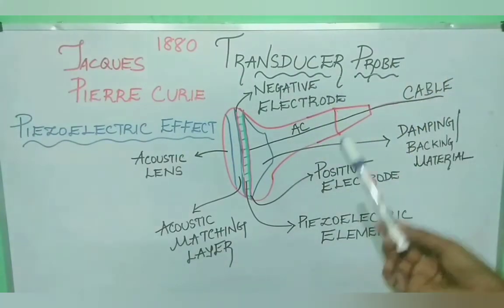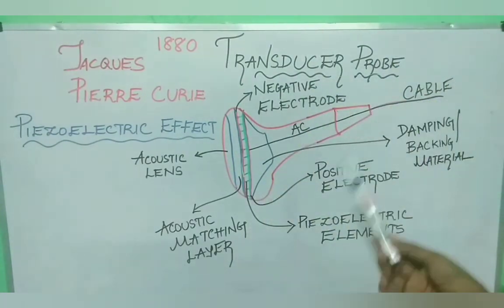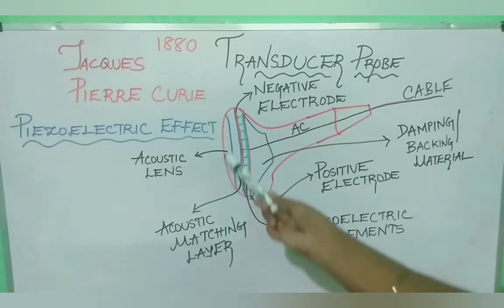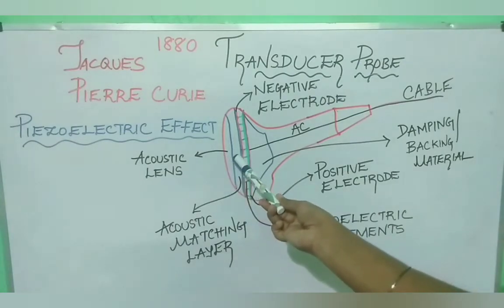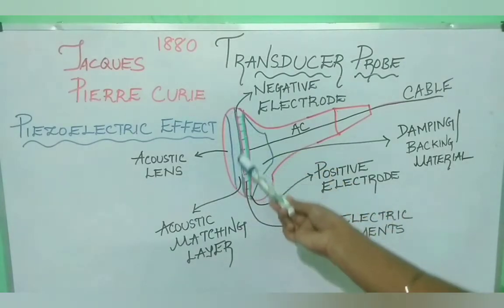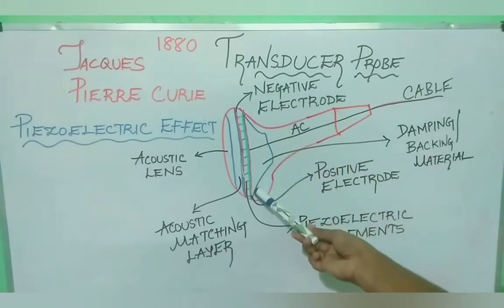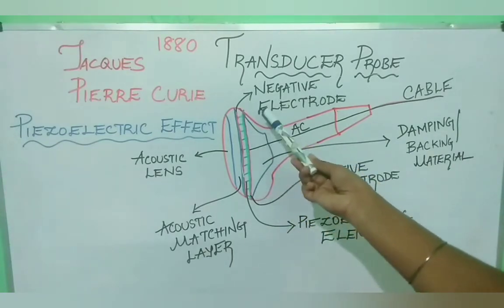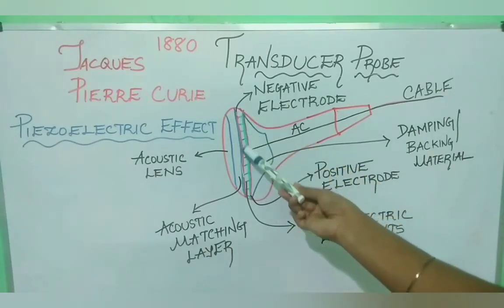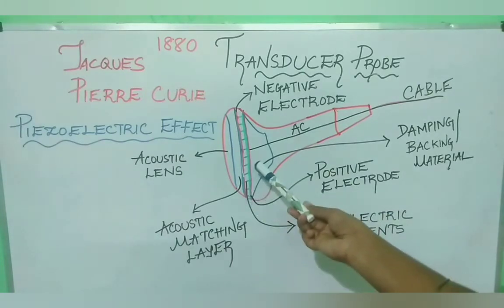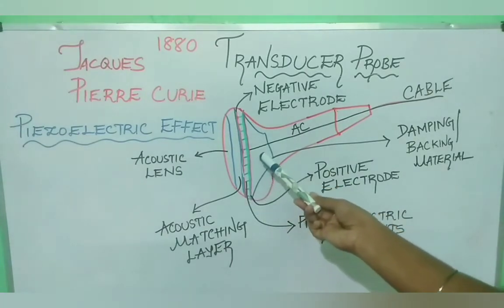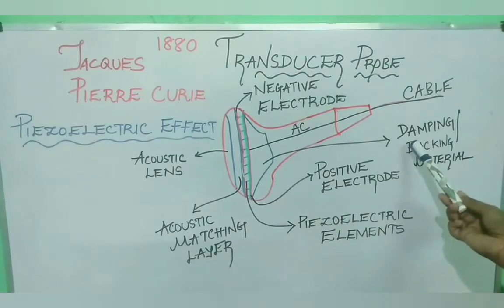A transducer probe is made of following components: acoustic lens, acoustic matching layer, negative electrode, positive electrode. In between both electrodes it has piezoelectric elements. Just behind the positive electrode it has damping or backing material.